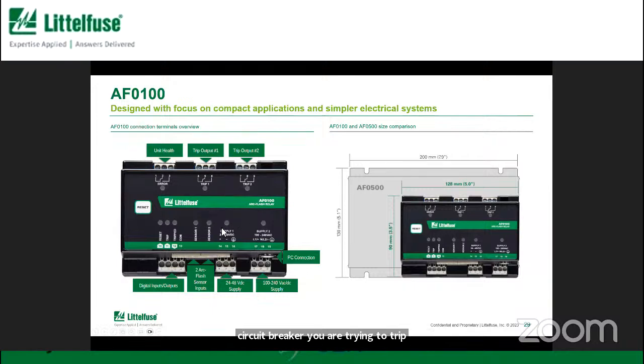Now I want to mention all 3 of these relays, the AF100, the AF500, the PGR 8800, they all have 2 power supplies. And this is again a redundancy feature. So you are able to have 1 power supply connected. You could have a low voltage DC or a line power 120/240, or you could have both of them connected at the same time. And if you connect both, the relay will operate. And if you ever lose one power supply, of course, the relay will stay powered from the other one, but it would give you an alarm, not a trip to shut down, but it would give you an alarm that you have lost one power supply.